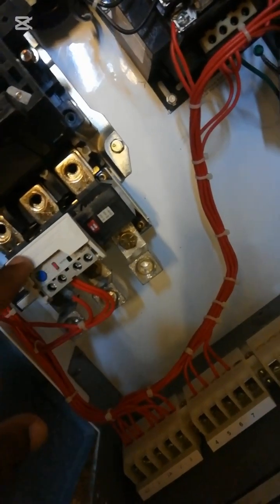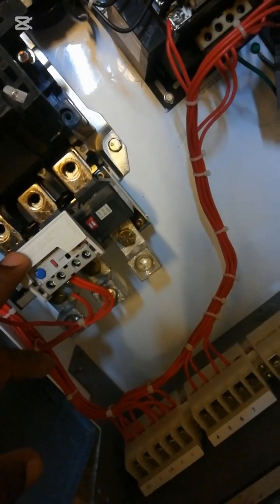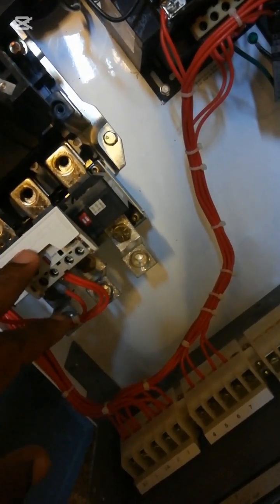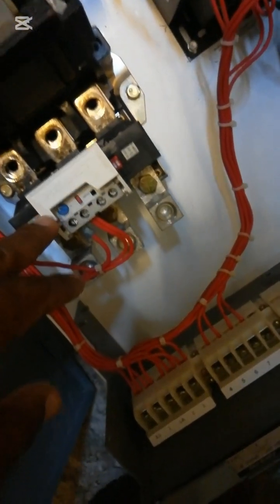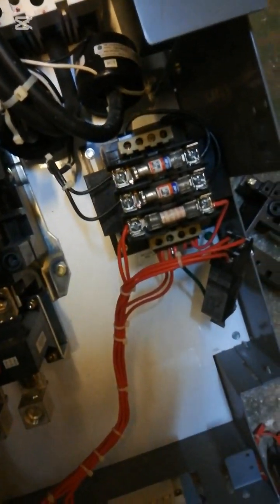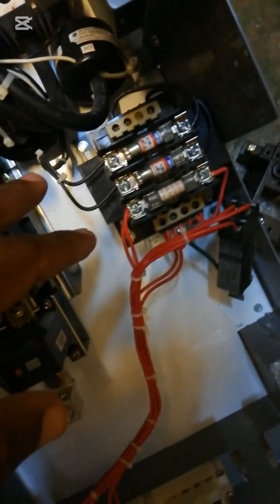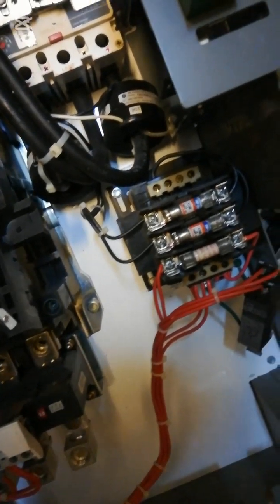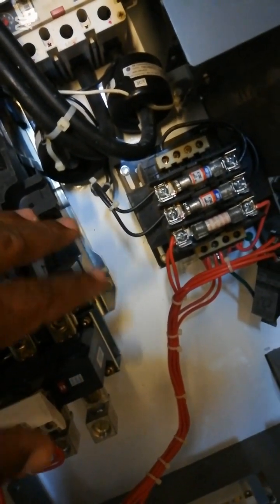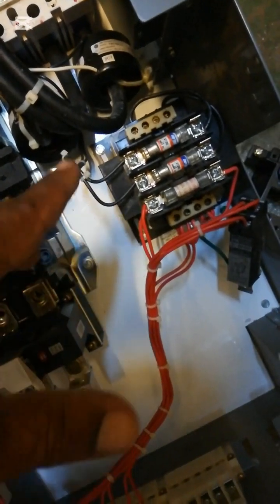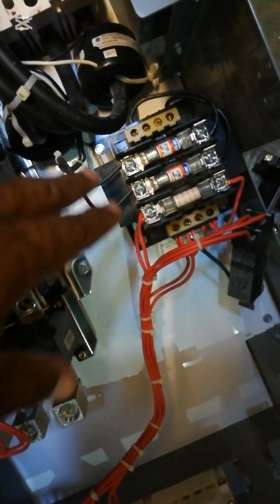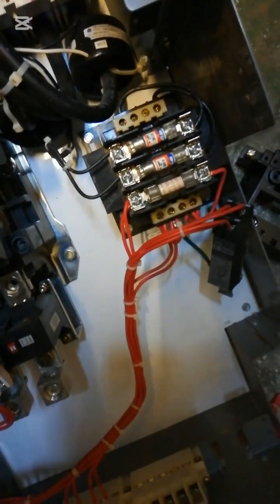It would pass through an overload system, which will open the circuit electronically if there is a high current more than the rating that it is set for. This would be a form of protection for the motor. And right here you have the fuse for the transformer. Transformer is a control transformer which steps down the voltage. This type of starter uses 400 volts AC. So it will step down the AC 400 volts by means of the transformer here, to the required control voltage. This one is a 110, and you have 3 fuses, one on the secondary, one on the primary, and then you have just the fuse there for the control circuit.